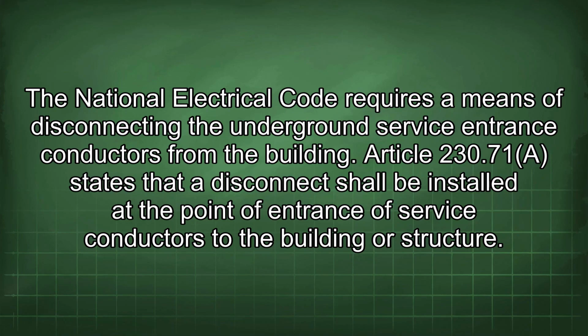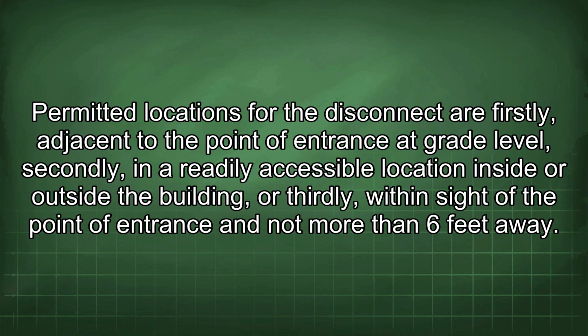The National Electrical Code requires a means of disconnecting the underground service entrance conductors from the building. Article 230.71 states that a disconnect shall be installed at the point of entrance of service conductors to the building or structure. Permitted locations for the disconnect are firstly, adjacent to the point of entrance at grade level, secondly, in a readily accessible location inside or outside the building, or thirdly, within sight of the point of entrance and not more than 6 feet away.